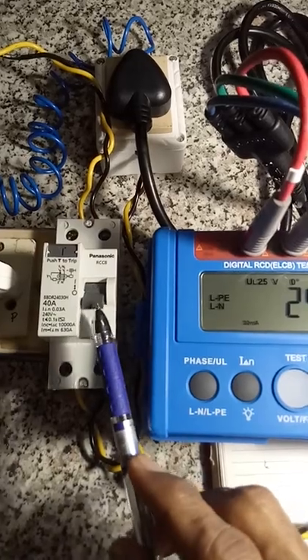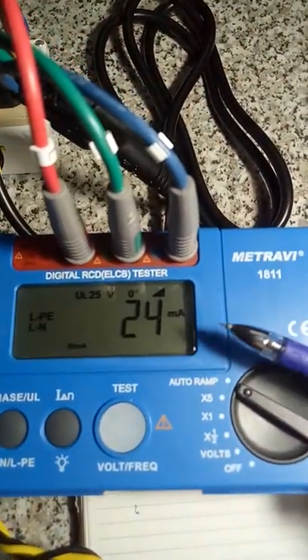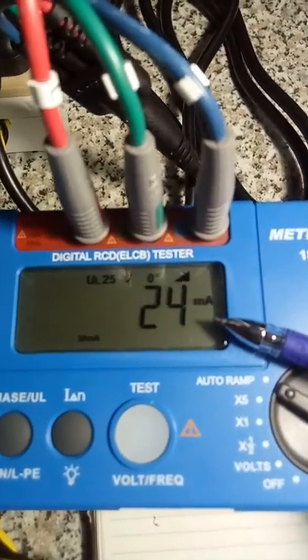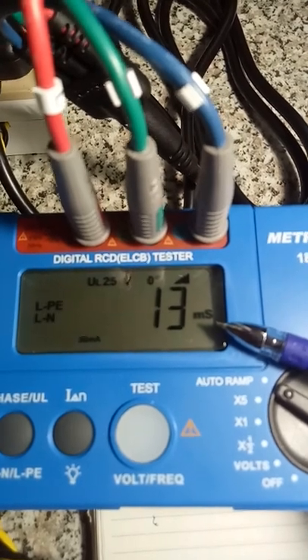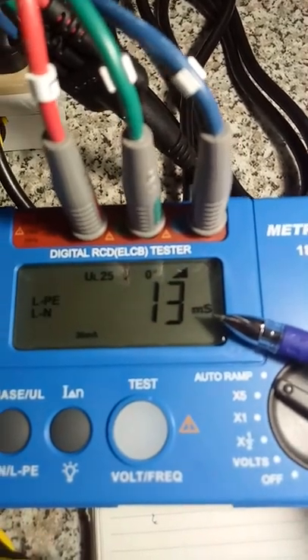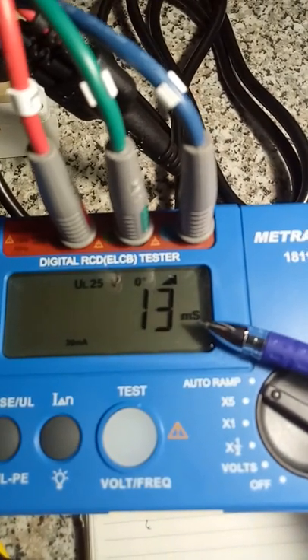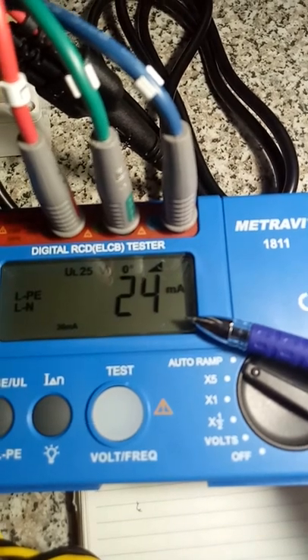So the RCCB has tripped. Here you can see the reading displayed simultaneously — 24 and 13. 24 is the milliamps and 13 is the milliseconds.